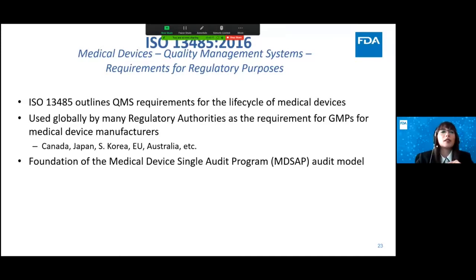Again, quality system requirements as well as ISO 13485 are requirements for the life cycle of the device. They are used globally by many regulators, such as Canada, Japan, South Korea, Europe, and Australia. So we do see value in being able to globally harmonize, and this is why our intention is to move in that direction. Currently we're making modifications to the regulation to recognize ISO 13485. And I already mentioned the Medical Device Single Audit Program is already based on that standard.